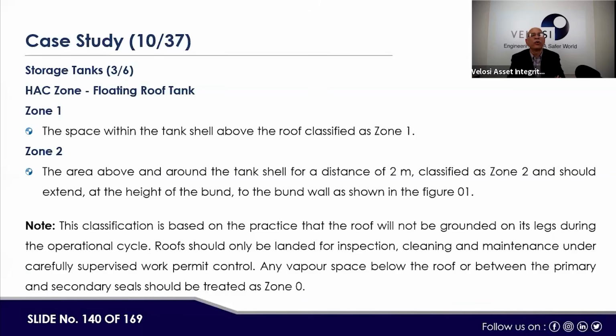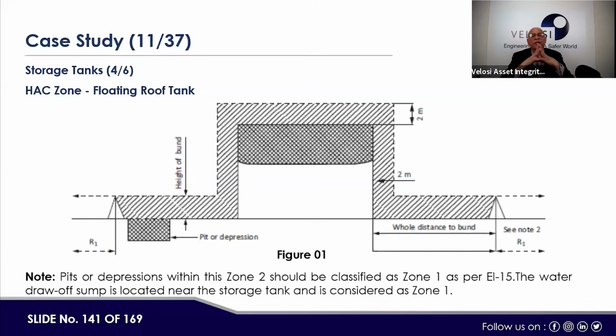Then HAC zone, floating roof, zone 1, zone 2, as we showed earlier. The space within the tank shell above the roof is classified as zone 1. The area above and around the tank shell for a distance of 2 meters is classified as zone 2 and should extend at the height of the bund to the bund wall, as shown in the figure. This is the figure we used, like this is the zone 0, then this is the zone 1 area, and here is also zone 1.